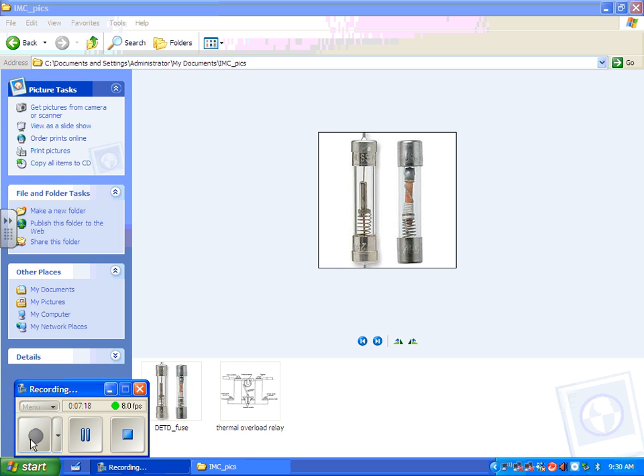If you look on page 37 of IMC, in the bottom half of the page, you see the solder pot overload relay. Now, we've talked about this picture before, in that we were talking about a mechanical starter, remember? And we said that it's only slightly different in the overload section, because it doesn't have an electrical contact in a mechanical overload.